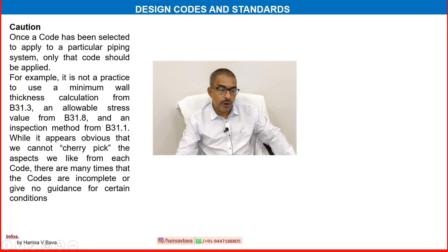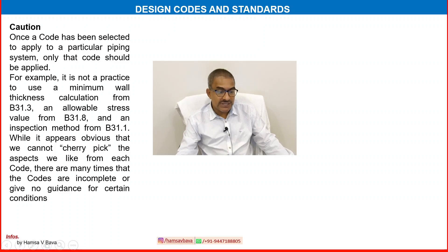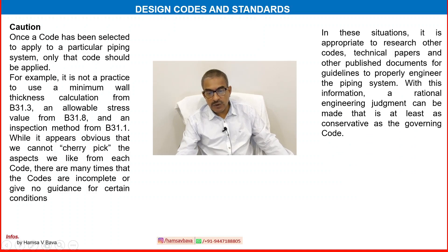Caution! Once a code has been selected to apply to a particular piping system, only that code should be applied. For example, it is not acceptable practice to use a minimum wall thickness calculation from B31.3, an allowable stress value from B31.8, and an inspection method from B31.1. While it appears obvious that we cannot cherry-pick aspects from each code, there are many times that codes are incomplete or give no guidance on certain conditions. In these situations, it is appropriate to research other codes, technical papers, and other published documents for guidelines to properly engineer the piping system, so that a rational engineering judgment can be made that is at least as conservative as the governing code.